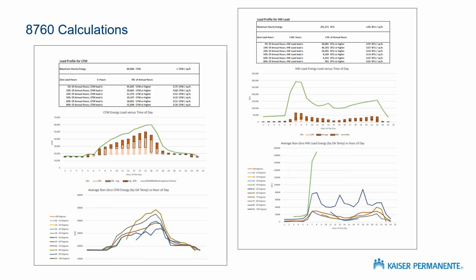This example here comes from one of our medical office building projects. And the one on the left there is for air handling unit CFM. And you can see it's an air handler designed at about a CFM per square foot, nothing unusual about that. But if you look at the load profile here, you'll see that 80% of the hours of the year, the calculated air is less than 0.3 CFM per square foot. Well, that could be a real problem because the standard rooftop package unit can only turn down to about 30 or 40%.